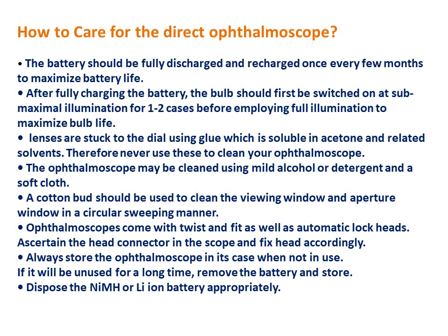It has to be at sub-maximal illumination for the first 2 or 3 cases before employing full illumination, to maximize the bulb life.